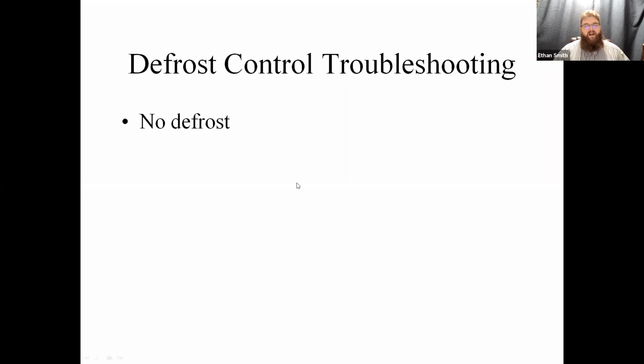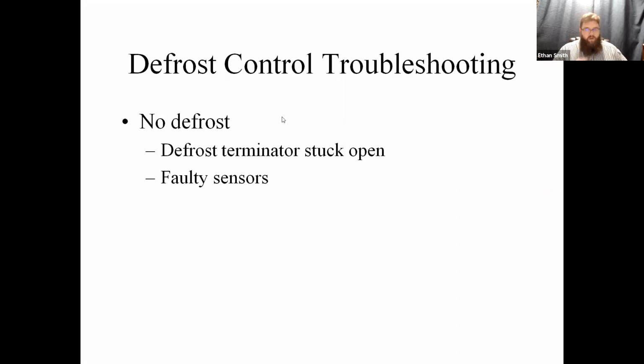So other times you'll see defrost problems is if the defrost is not working at all. So your terminator may be stuck open. Most of the defrost systems out there will have a maximum defrost time programmed into them. It's usually on the order of like 15 minutes though. So if your terminator is stuck open, it may run for up to 15 minutes and then reverse cycle. That's usually due to a faulty sensor. You can also have bad timers where it just never comes out of defrost.